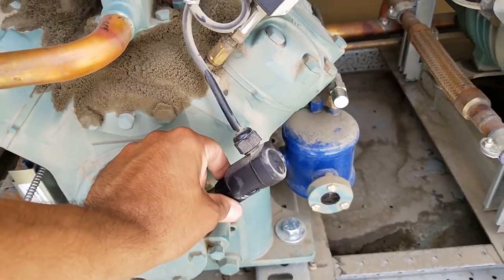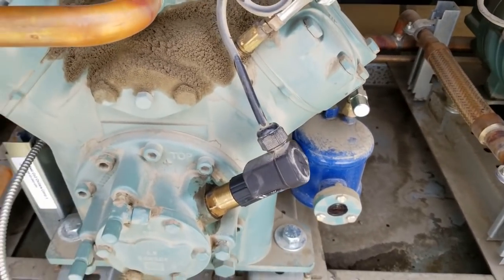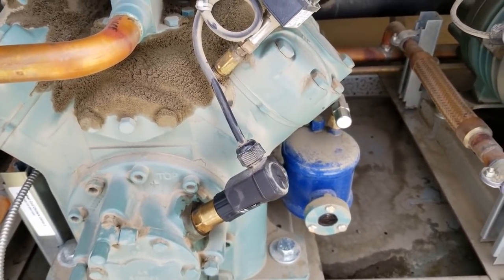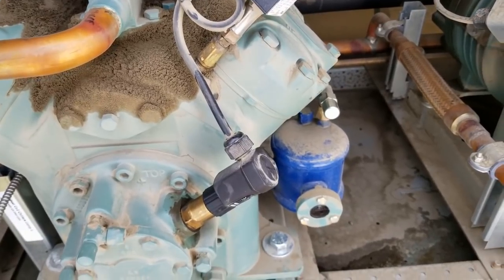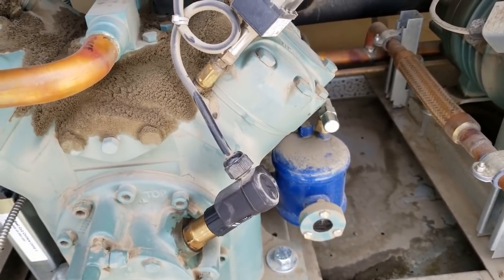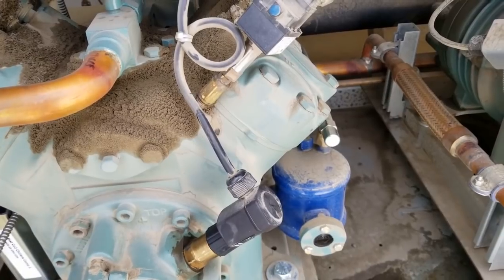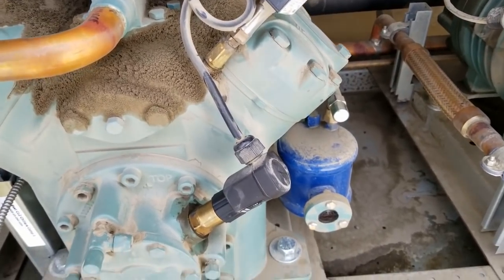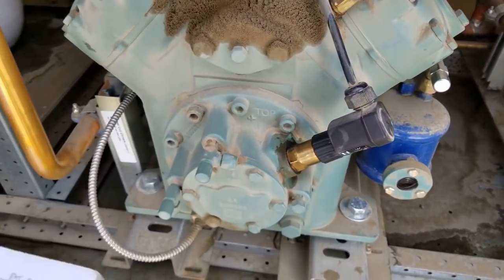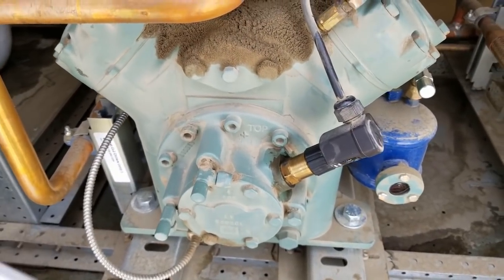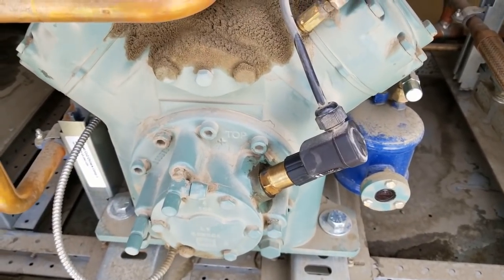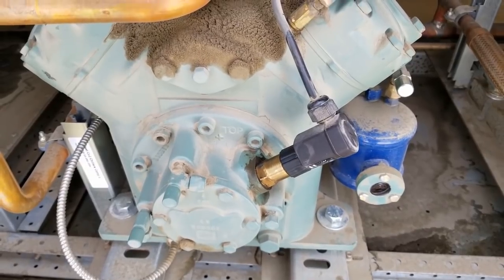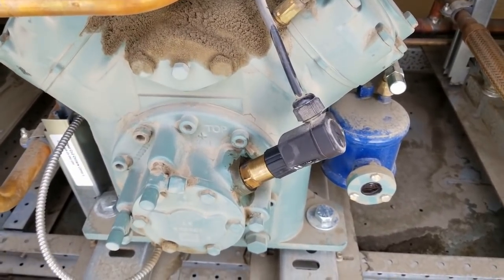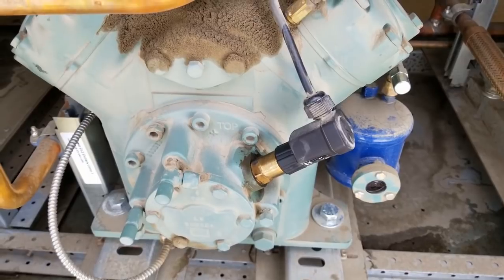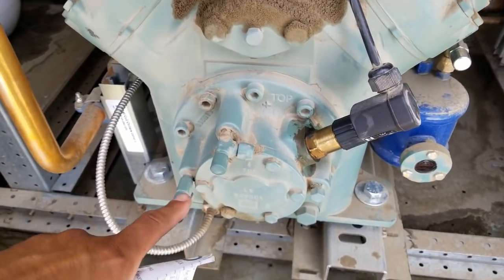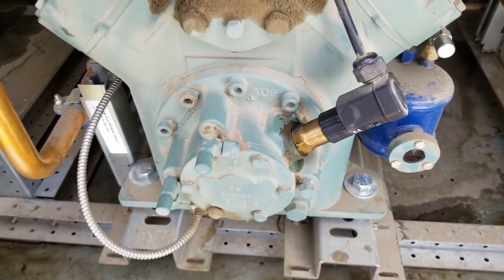So this only goes off of your differential. He said the differential on this would be a swing - I'm trying to find my numbers here - a swing of 20 to 50 differential on my Delta P. The absolute minimum would be 10 differential, and it trips on 9 differential. So on my oil pump right here, this is where you would check the differential.